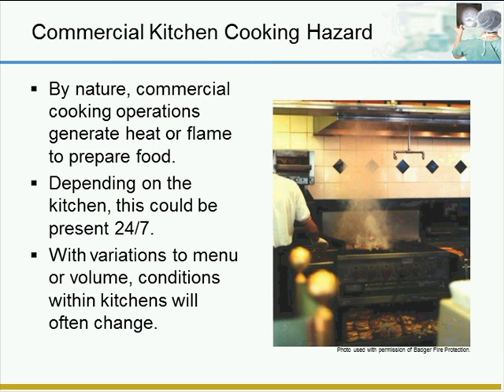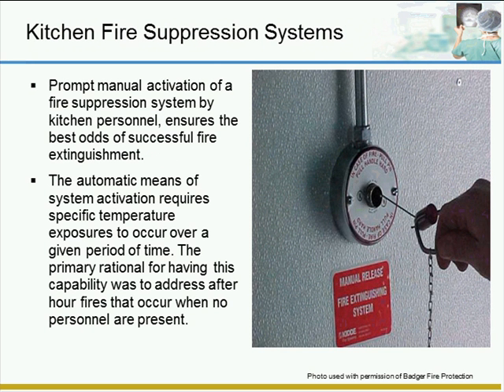Most healthcare facilities have cooking facilities similar to the one shown here. Cooking is the number one cause of fires in healthcare facilities. All commercial cooking wet chemical extinguishing systems have a remote manual activation switch, which is very similar to this one. The kitchen staff must be trained on when to activate the system manually. The system will operate automatically with fusible links located in the duct and hood area of the exhaust system. But there is an opportunity for the kitchen staff to manually operate the system to prevent spread of the grease fire up into the duct and hood, and they should be trained on this.